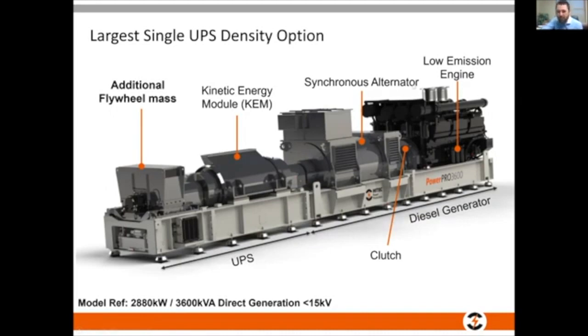We've got our standard diesel generator. This is a much bigger engine than what I showed you before. This is probably a 20-cylinder MTU, by example. We've got a much bigger alternator. Now, that is actually medium voltage, what I'm showing you, because the higher you get in power, the more likely you are going to go medium voltage, just to reduce the conductor size, maybe to reduce the switchgear. Maybe you're limited by the switchgear itself. So I'm showing you a 2.9 or 3 megawatt, let's say, diesel generator. I've got my flywheel that I mentioned earlier. It looks a little different. It has to work a little differently. But by virtue of going to more power, I need more ride through.